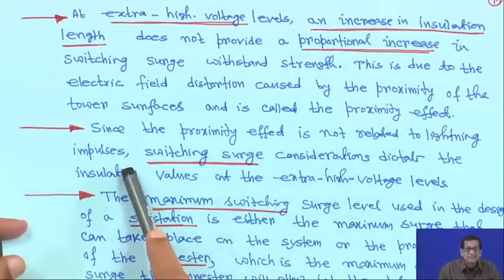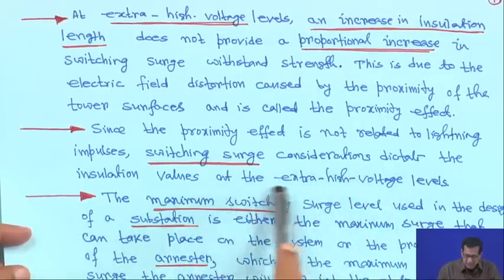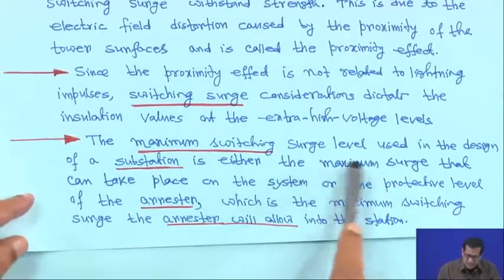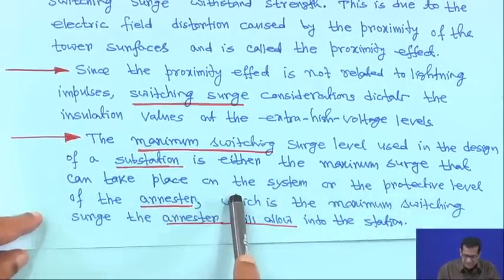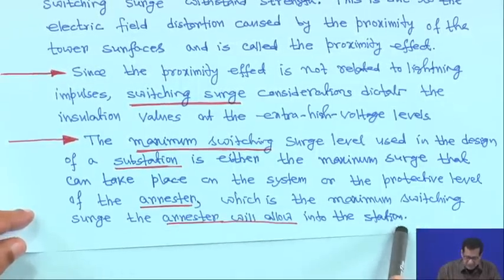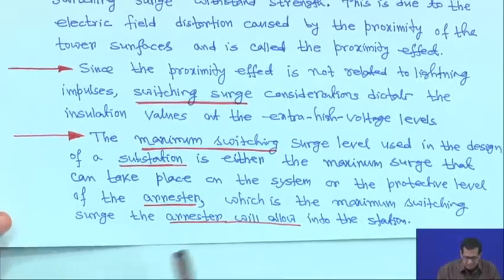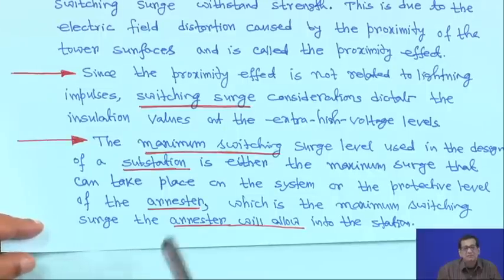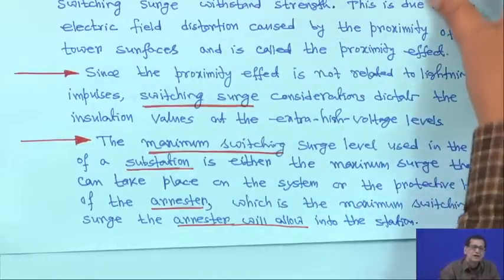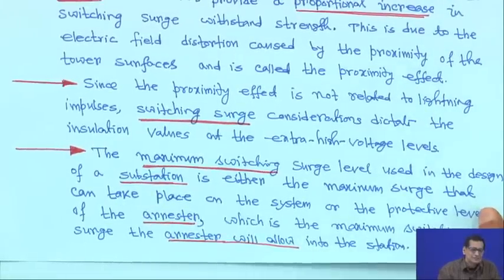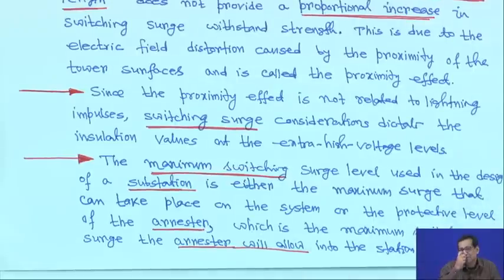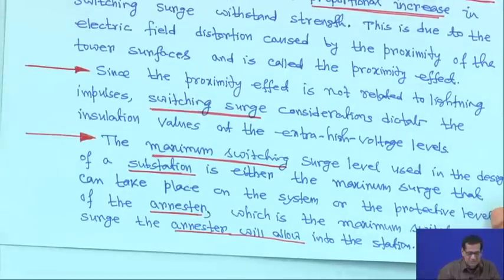The maximum switching surge level used in designing a substation is either the maximum surge that can occur on the system or the protective level of the arrestor — that is, the maximum switching surge the arrestor will allow into the station. Even arrestors can fail due to heavy lightning strokes; such arrestor failure can cause damage to other equipment in the substation.